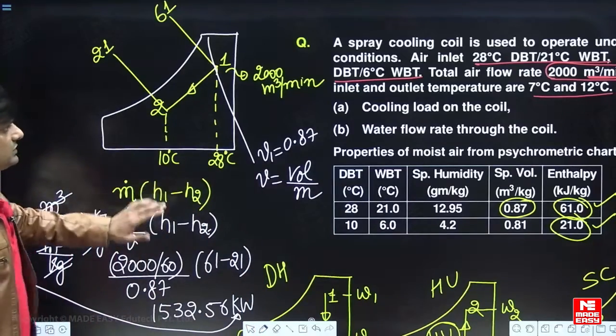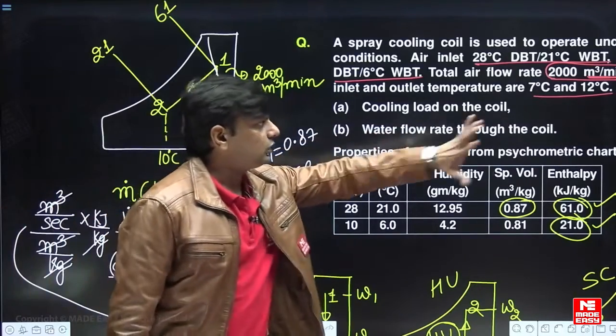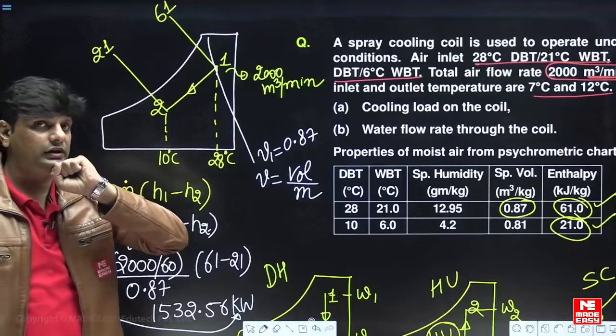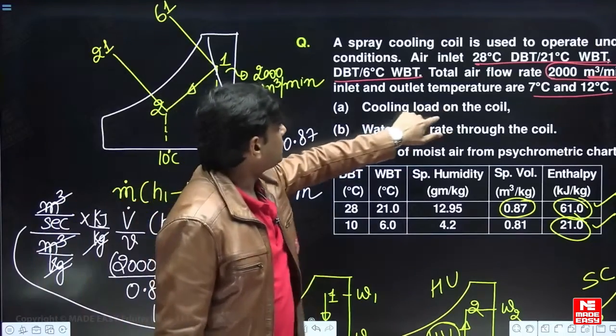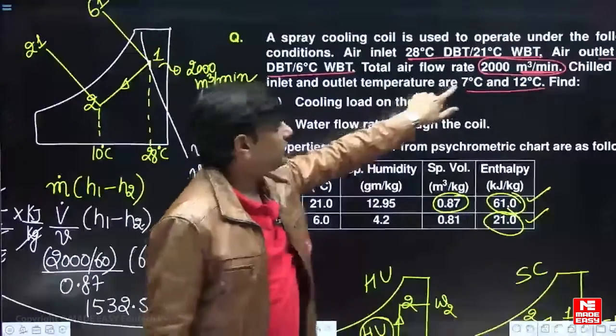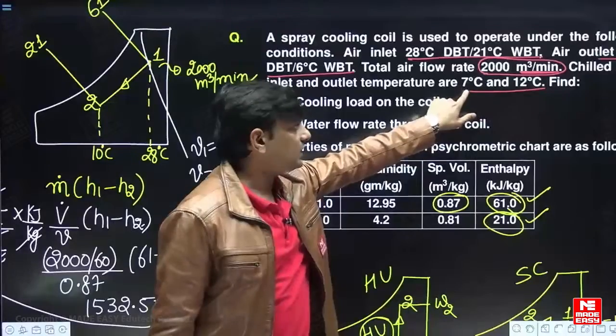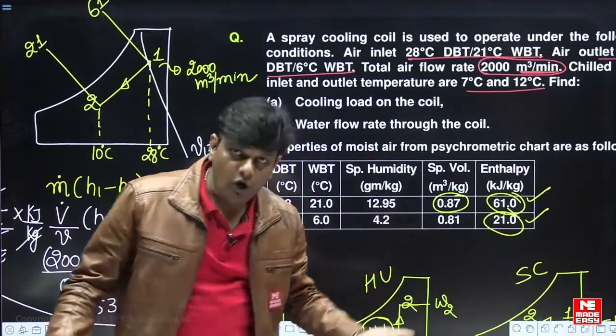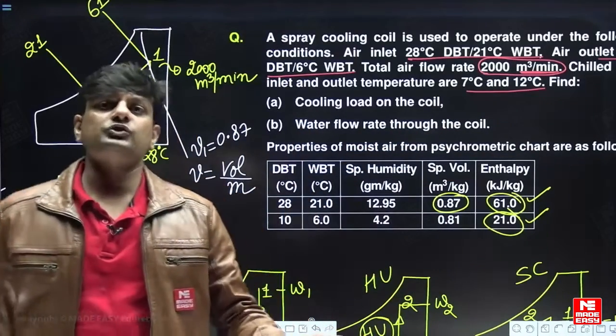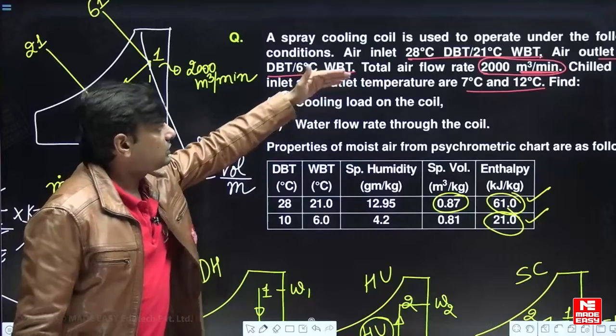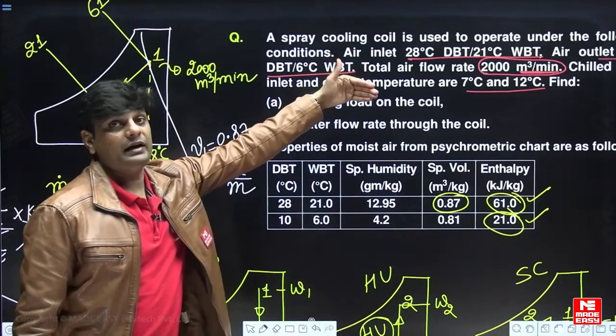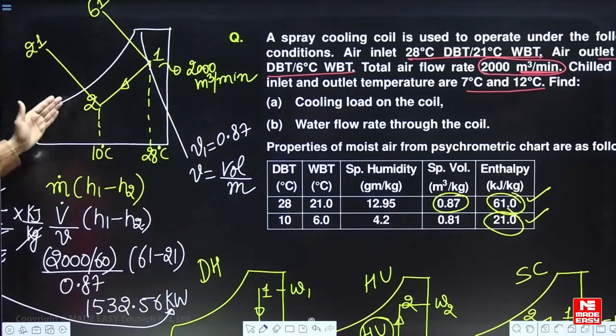So m dot h1 minus h2. Now water flow rate through the coil. Why are they asking for water flow rate through the coil? Because the chilled water inlet and outlet temperature are given, meaning the water is entering at 7 degrees and leaving at 12 degrees. Obviously the temperature of the water has to increase. Why? Because the increase in temperature equals heat gained by the water, and that equals heat lost by the air.